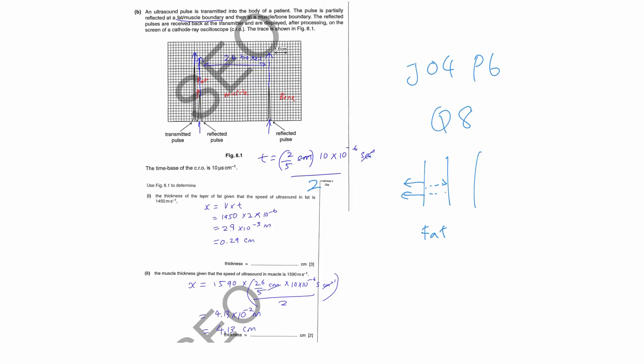And for muscle, it's the same thing. You count the number of boxes from here to here, which is 26 boxes. So 26 boxes over 5 boxes gives you centimeters. Then you multiply by the time base, which is 10 microseconds per centimeter, to get total time. Again, you must divide by 2. Then you multiply by your speed and you get your thickness.